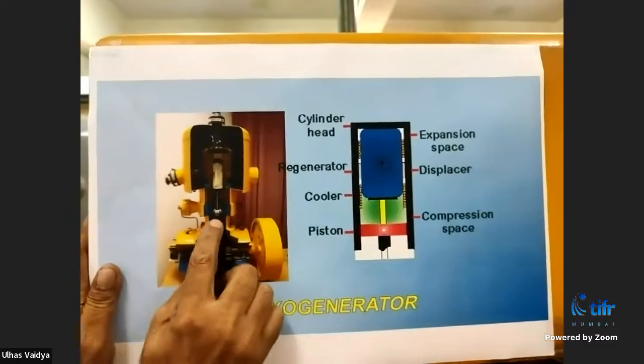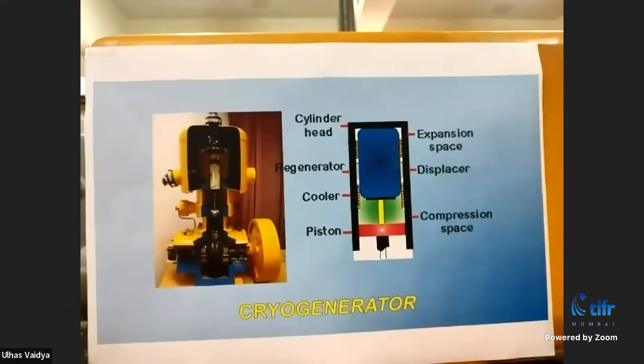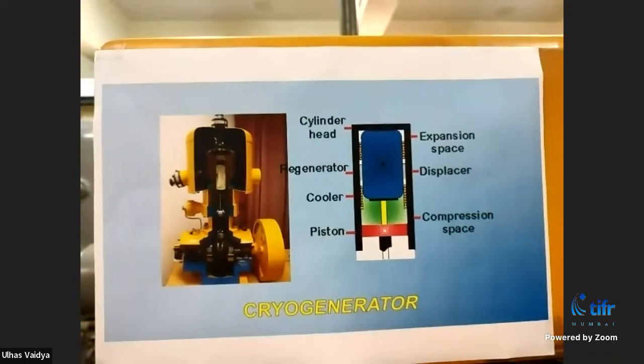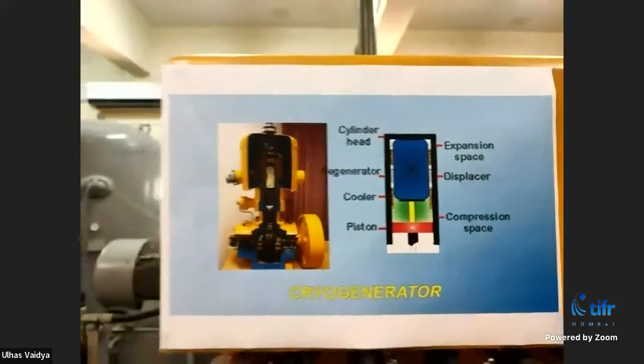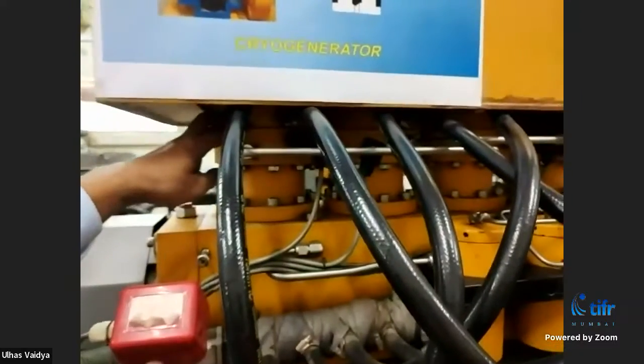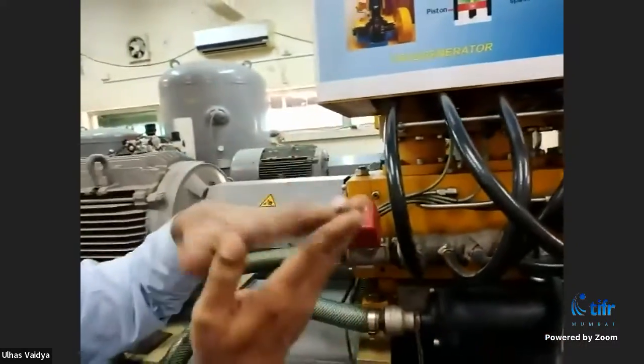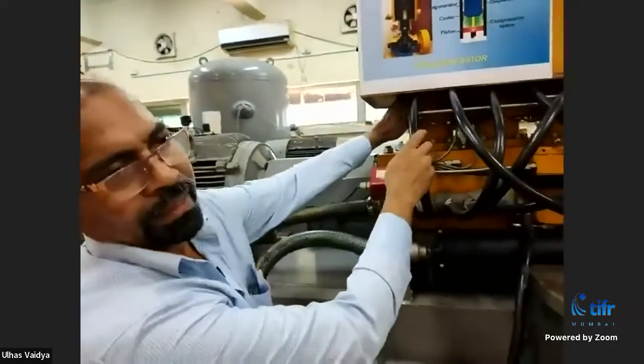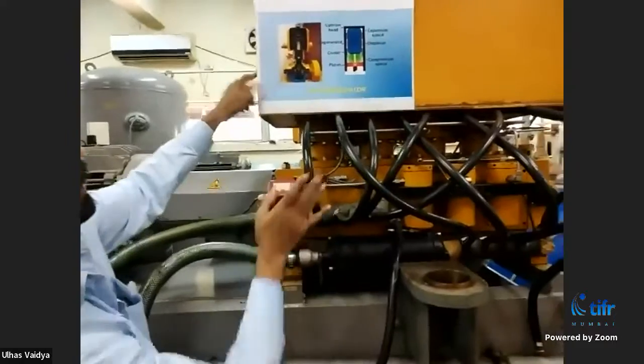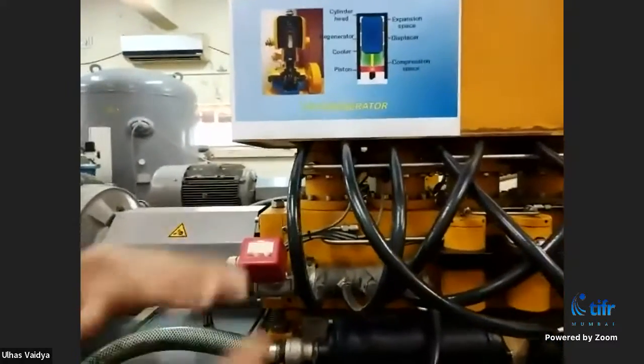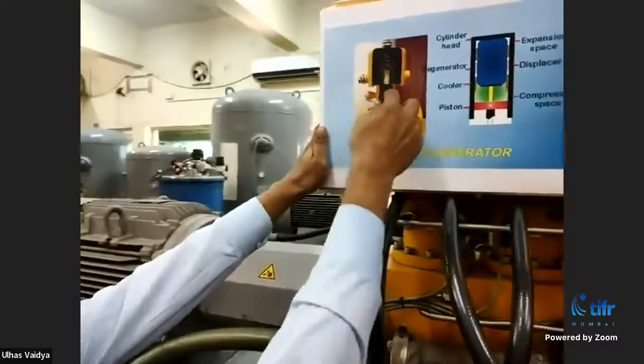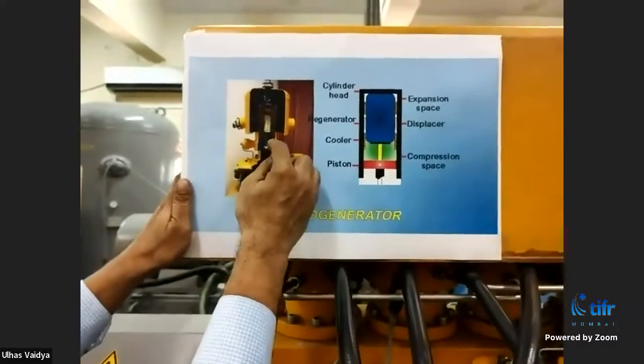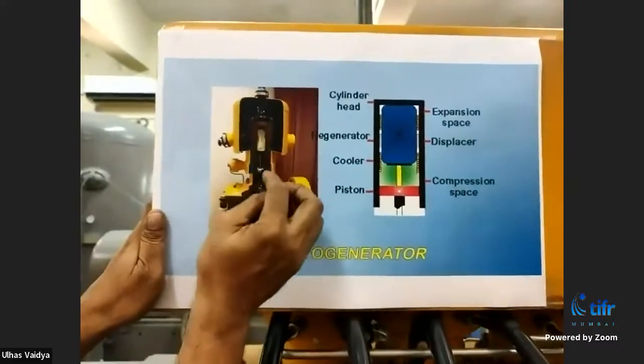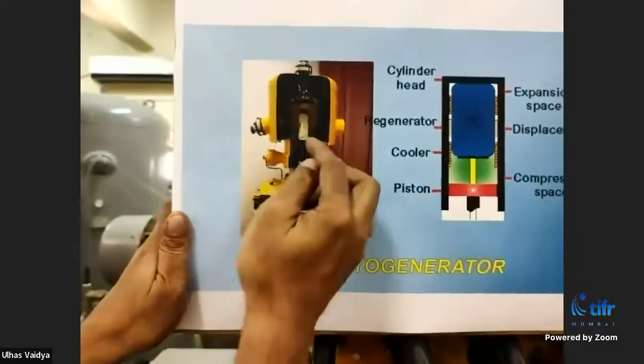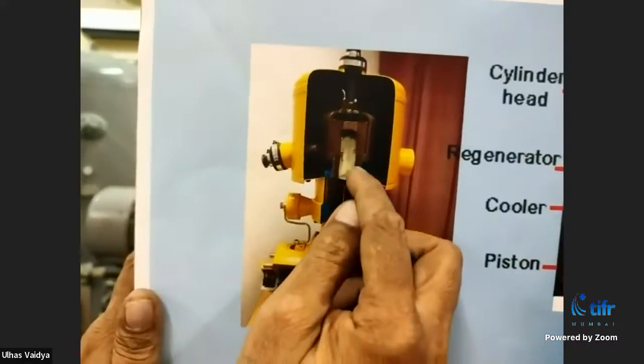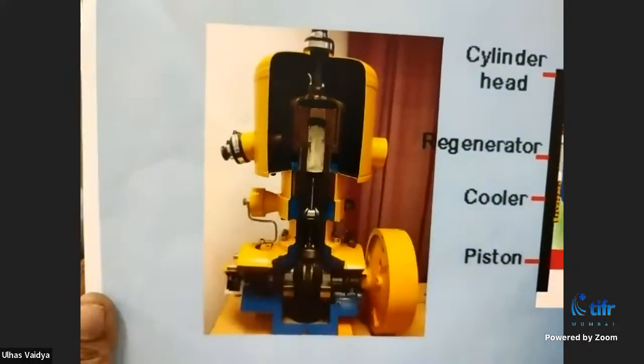So this piston moves up and compresses the helium. After compression, helium goes upstairs through water coolers, similar to the condenser coils we saw in the refrigerator and liquid nitrogen setup. The water cooler, cooled by chilled water, removes the extra heat of the helium, and then it goes through a component called the regenerator, which is a key component of this cryogenerator, and then to the upper space, called the expansion space.